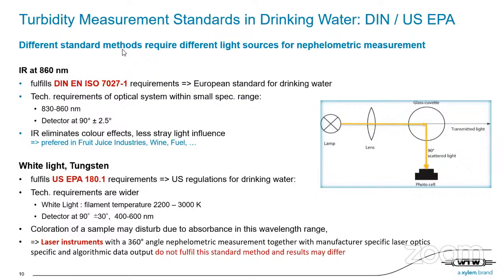Also, we have different drinking water standards in the world, and as far as I know, Mexico probably is more with white light tungsten, but others are with IR, DIN, EN, ISO. And in some countries you can choose. So the DIN ISO technical requirements are a little bit more within a smaller range of specifications. And IR has the advantage itself that already the light source eliminates color effects. You know, if you think about photometers, that color leads to an absorbance in a light source, and at the near infrared and infrared, there the color cannot absorb anymore. So this is why we have a European standard drinking water with IR.